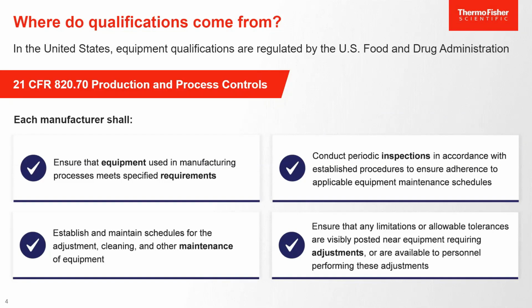Where do qualifications come from? In the United States, equipment qualifications are regulated by the U.S. Food and Drug Administration. 21 CFR 820.70 Production and Process Controls tells us each manufacturer shall ensure that equipment used in manufacturing process meets specified requirements, establish and maintain schedules for the adjustment, cleaning, and other maintenance of equipment, conduct periodic inspections in accordance with established procedures to ensure adherence to applicable equipment maintenance schedules, and ensure that any limitations or allowable tolerances are visible, posted near equipment requiring adjustments, or are available to personnel performing these adjustments.